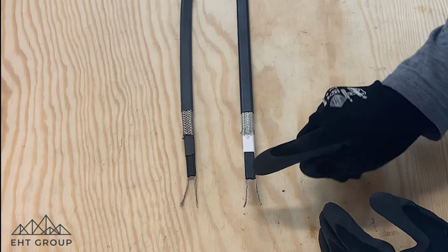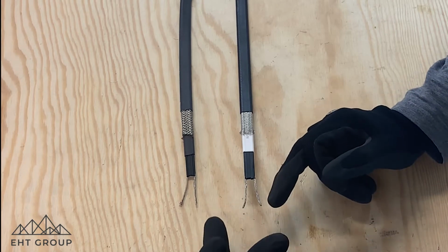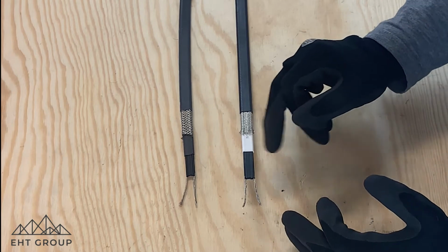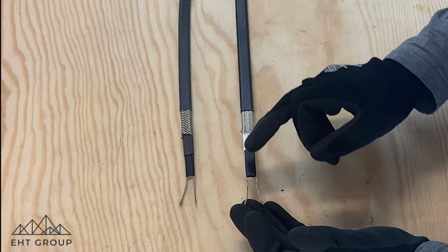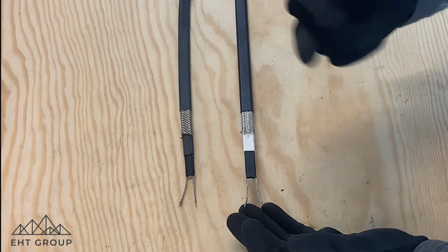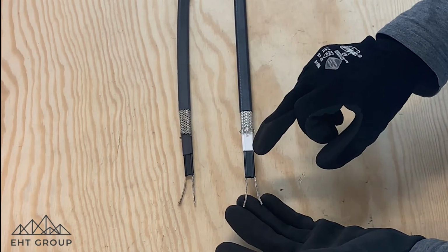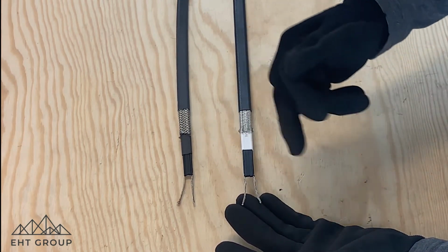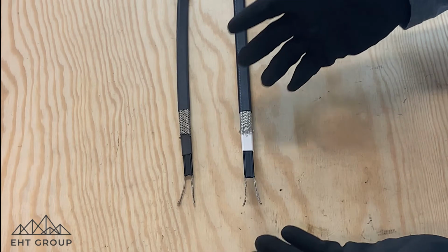And this black part in this cable, for instance, is actually what's generating your heat between our two electrical bus bars. So for certain SR cables, this conductive polymer will look just like this. The actual inner spacing here will be our semiconductor. For other cables, specifically cables that might be used for higher temperature applications or higher temperature maintain applications, what we'll see here is actually a spacer between the two electrical bus bars, and then we'll see a wrap, or a conductive polymer wrap, around the two bus bars. But the principle of this SR cable is the exact same.